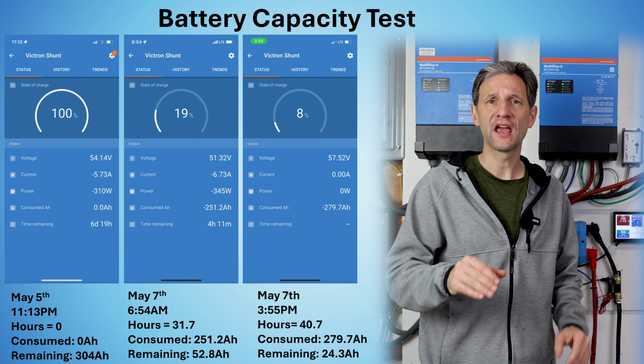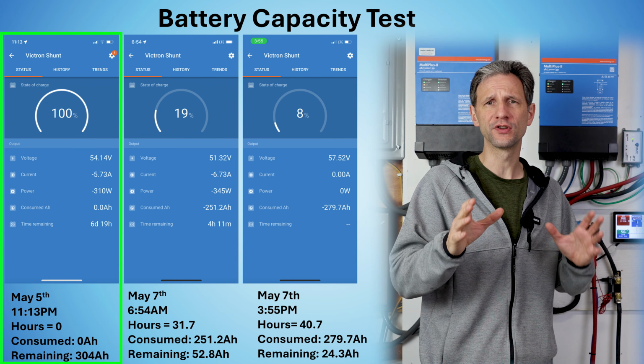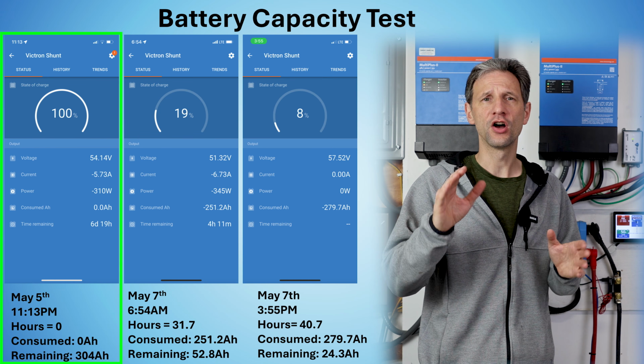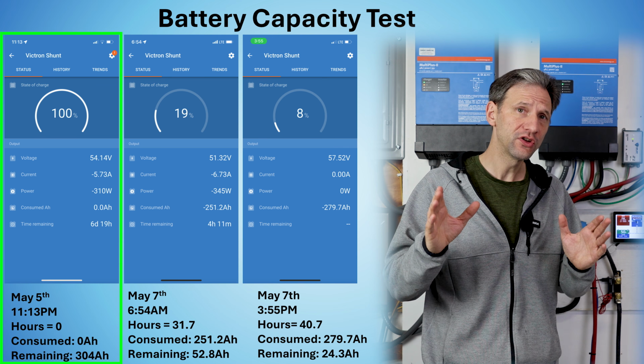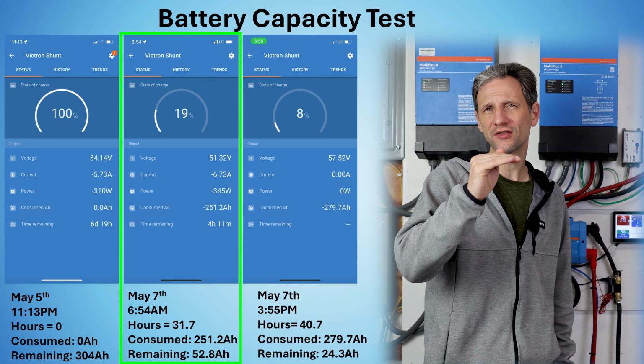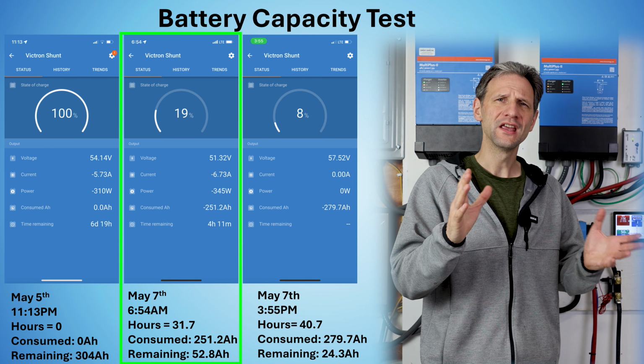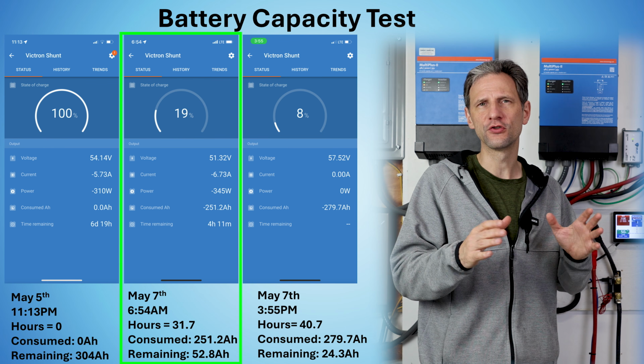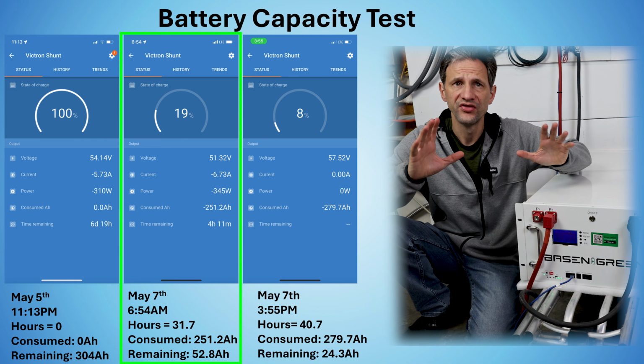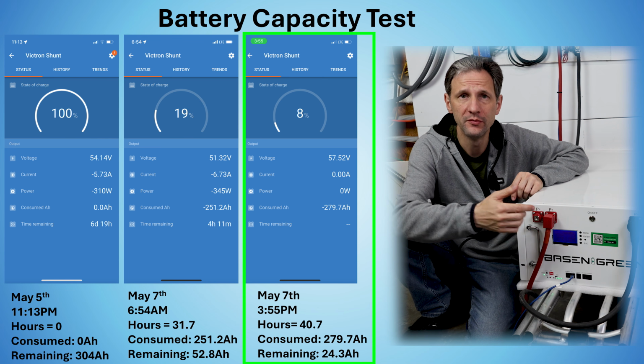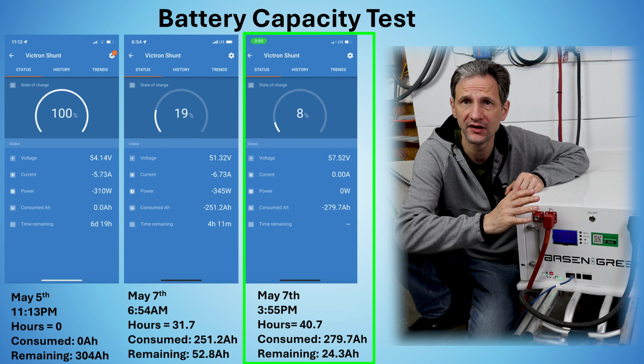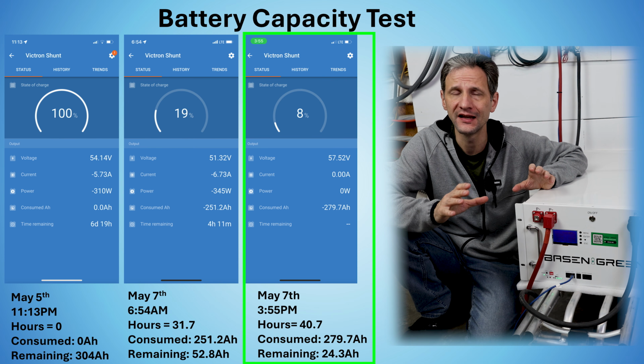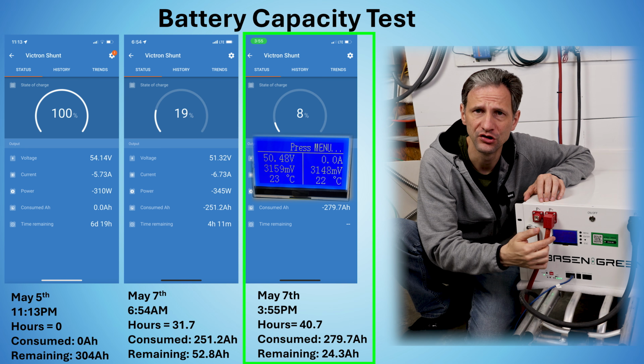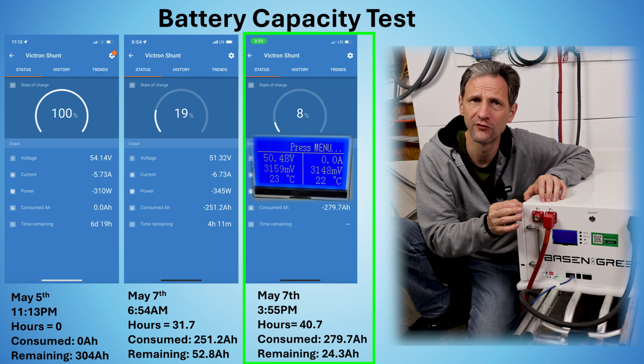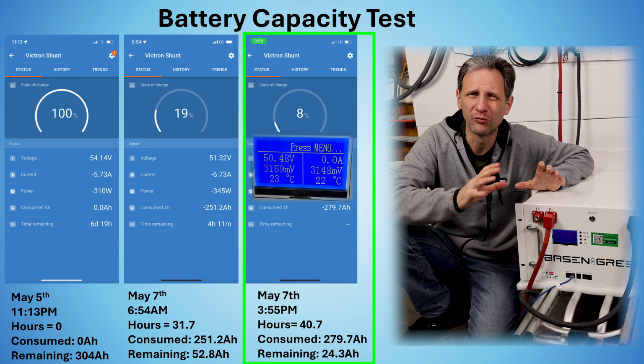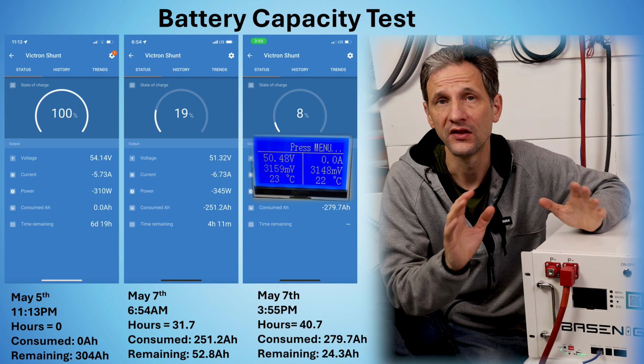I started the test at 100% state of charge, which was 54.14 volts under a little bit of load. It took almost 32 hours to drop the battery to just under 20% capacity, a typical stopping point if you're trying to extend the life of your battery. Then at about 40.7 hours, the BMS cut the power at 8% capacity, or about 280 amp hours. A picture of the BMS menu shows a voltage of 50.48 volts, so under load it probably dropped below 50 volts. That's a very nice result.